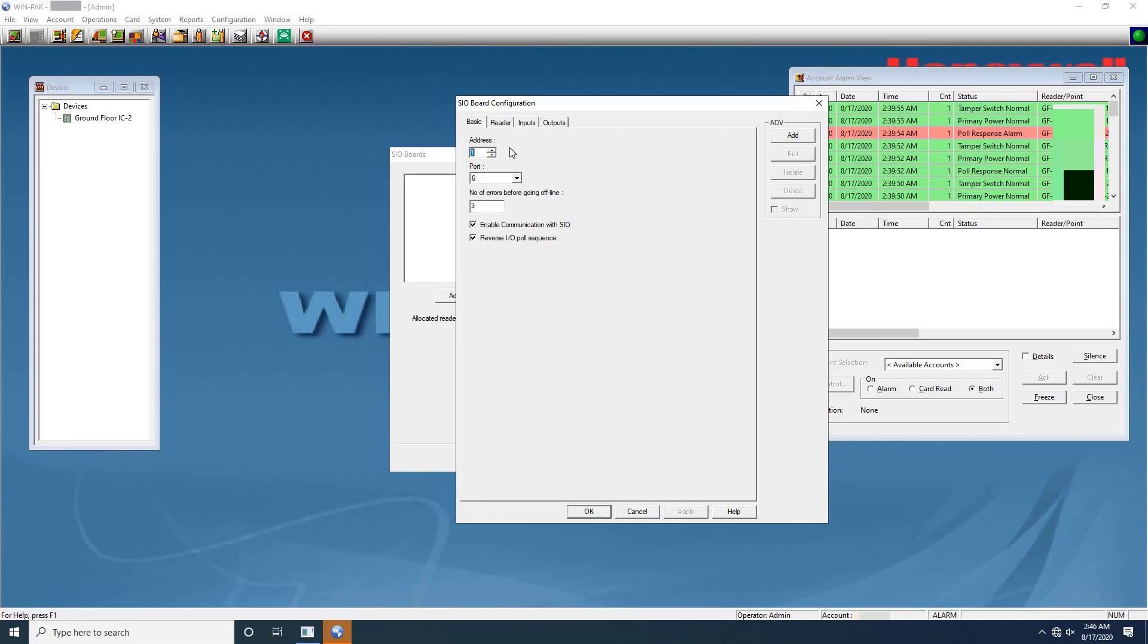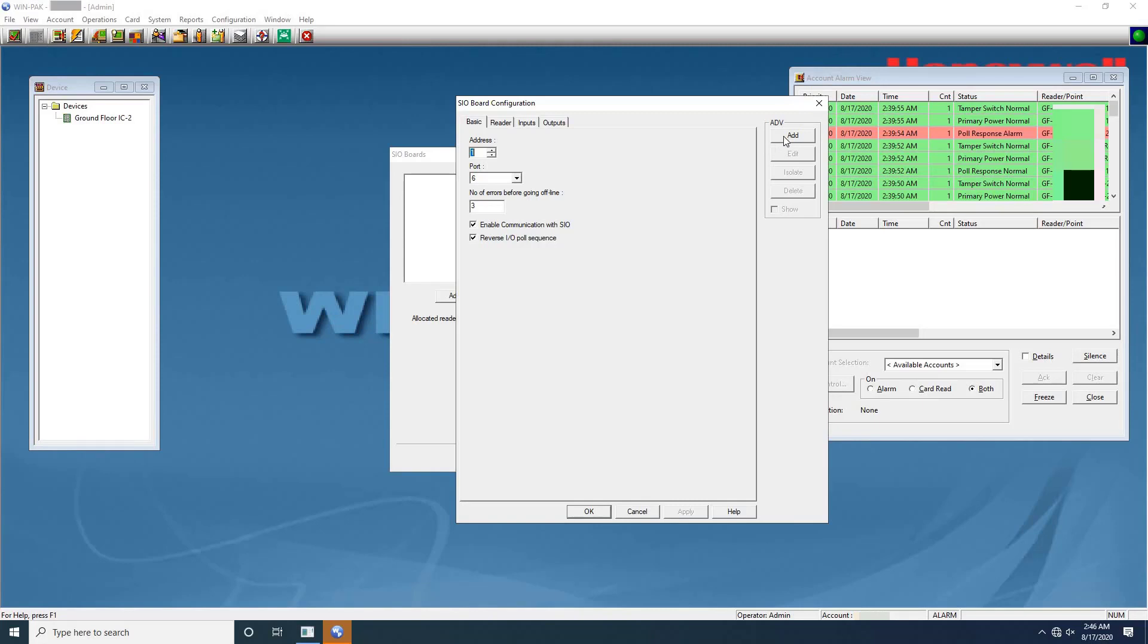Next in the port list, select the port from which the board communicates with the intelligent controller. Keep it as default port number. Next number of errors before going offline field. Type a number of attempts the panel must make to communicate with the communication server before tripping the offline trigger. This field defaults to 3. Next select the enable communication with SIO checkbox for enabling connection with the SIO board. Select this checkbox only if the board is installed.